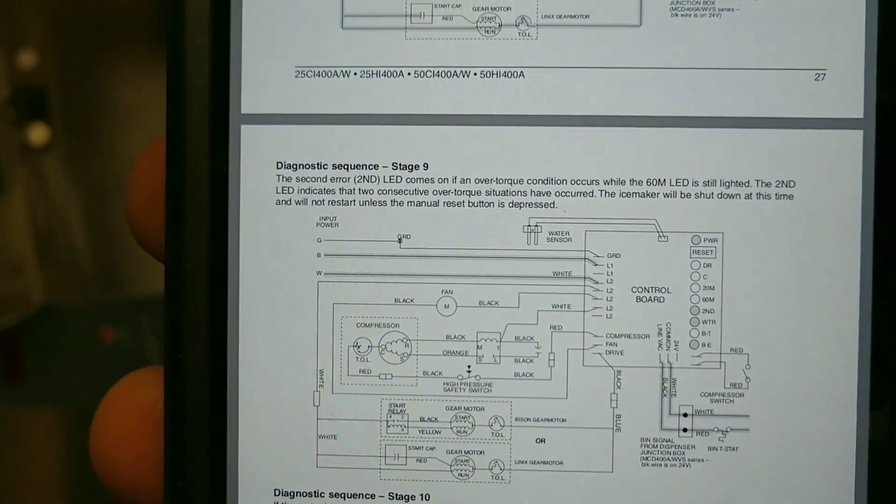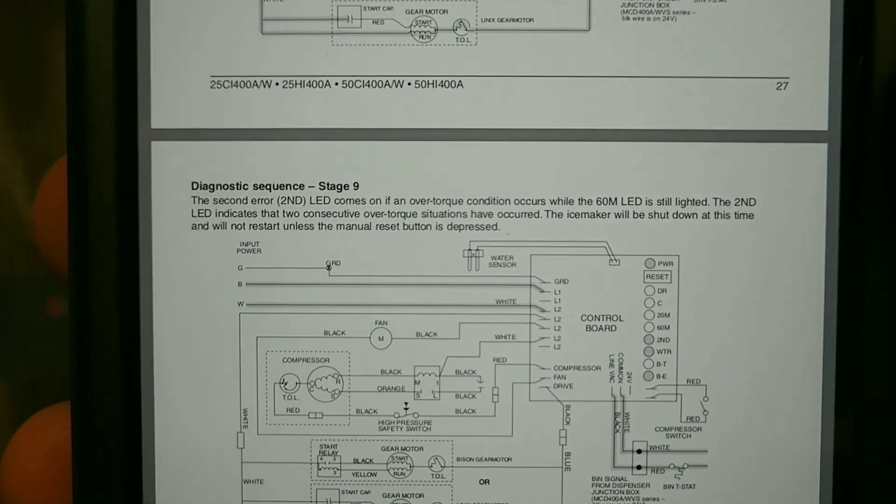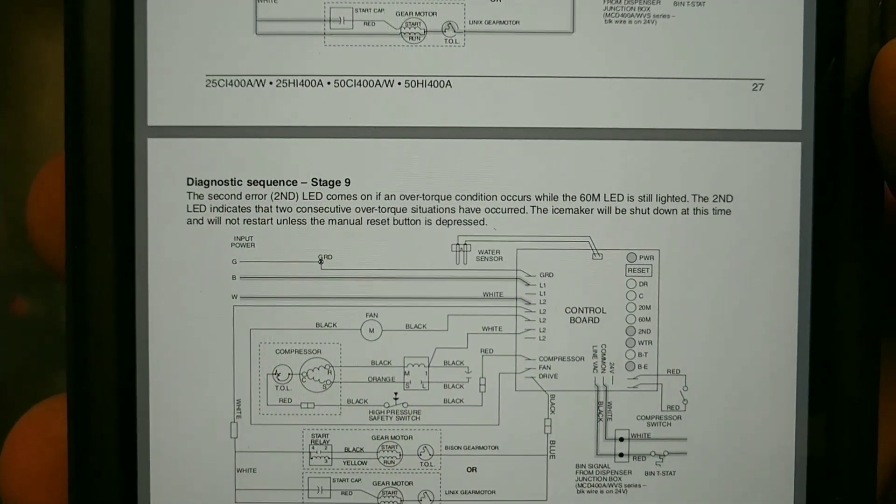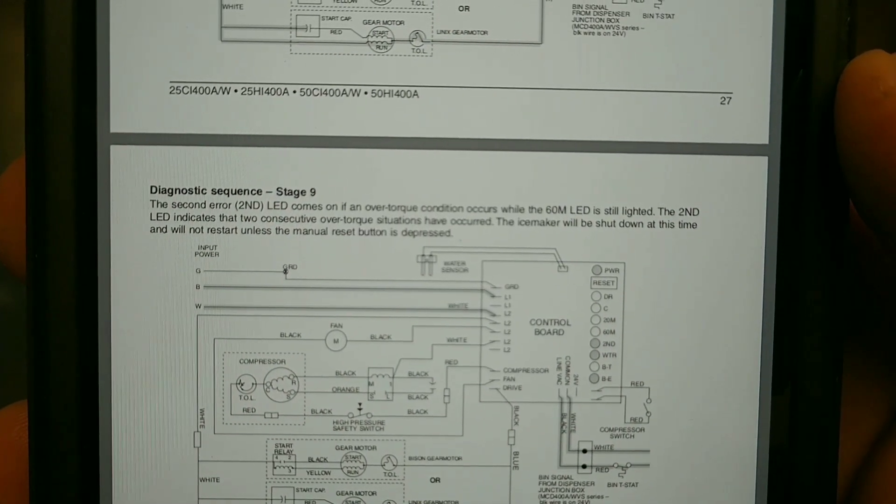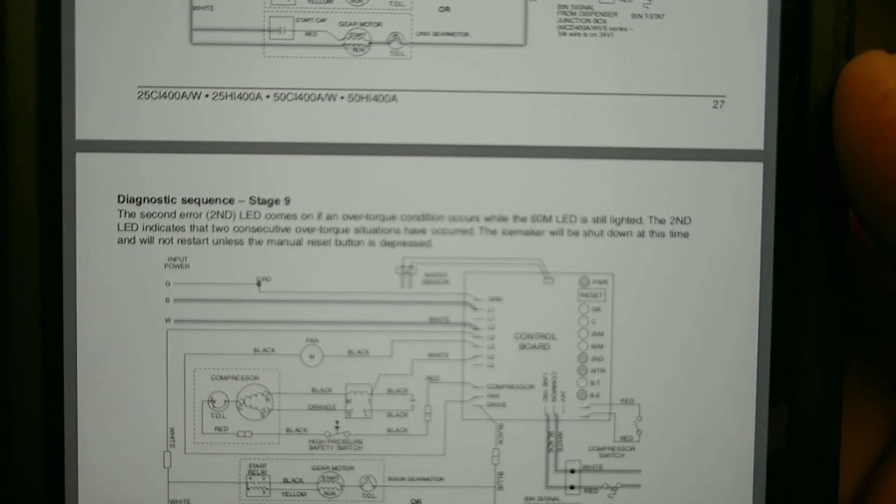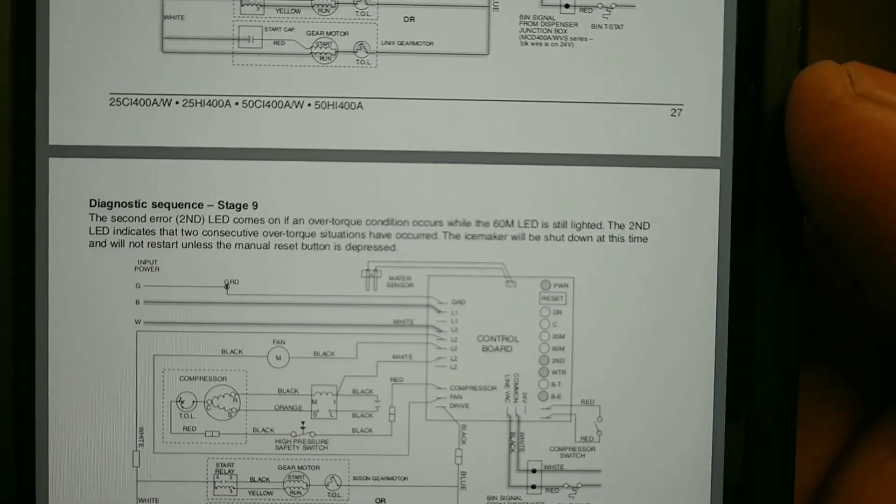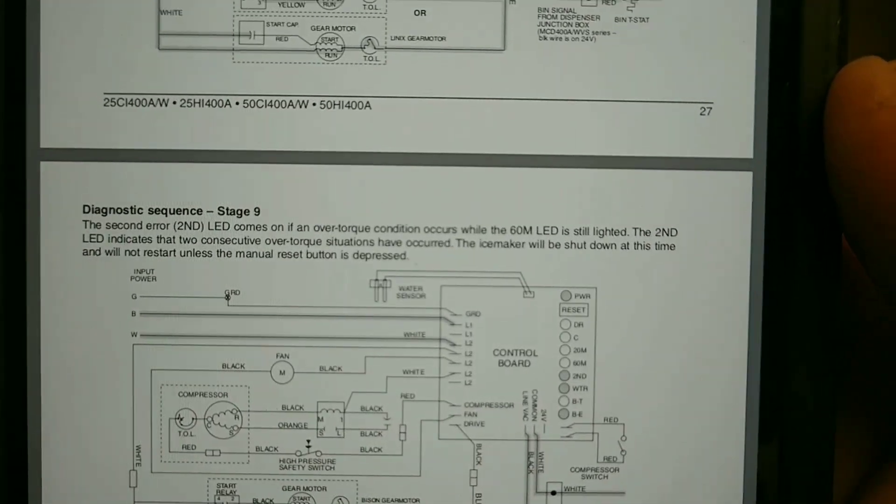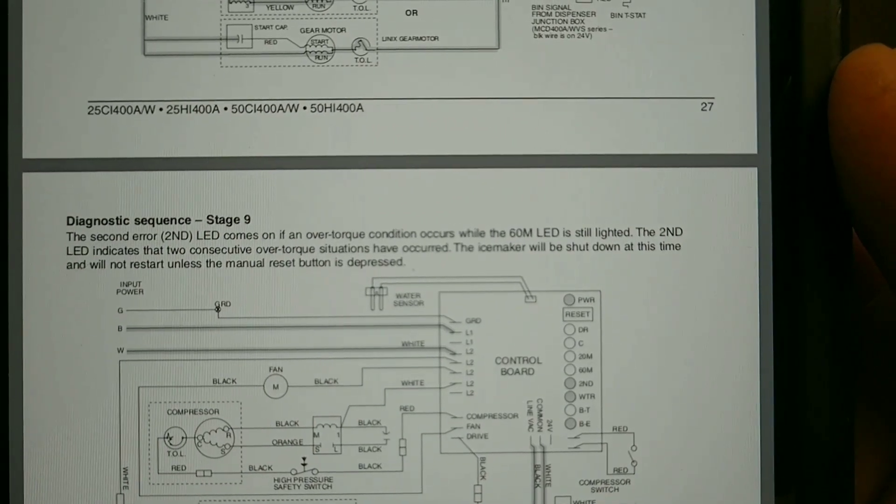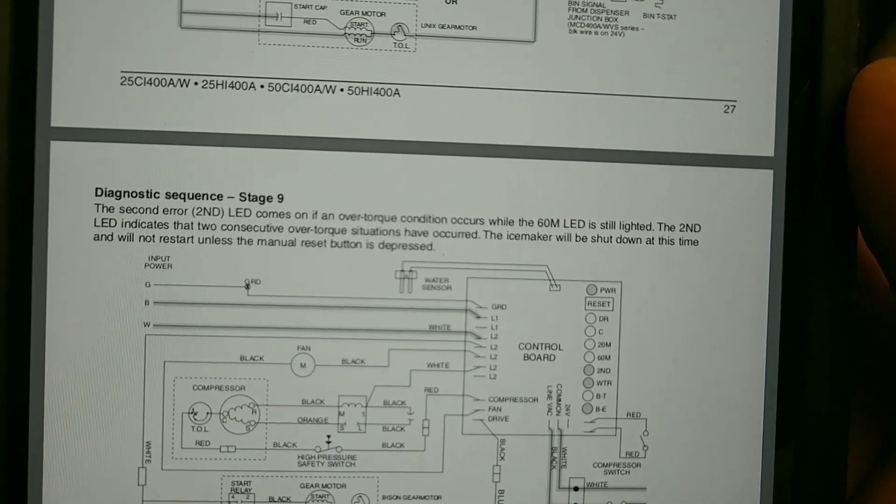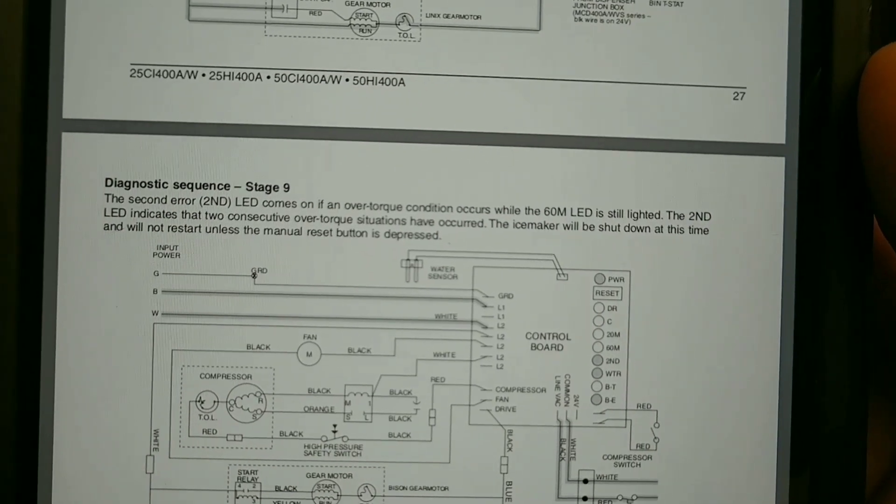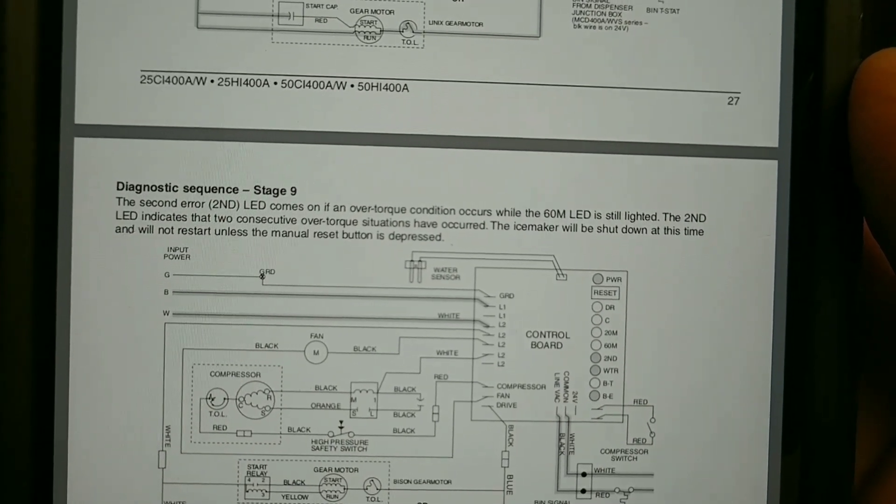But it didn't, because we also had our second LED. The second LED comes on if an over torque condition occurs while the 60m LED is still lit. The second LED indicates that two consecutive over torque situations have occurred. The ice maker will be shut down at this time and will not restart unless the manual reset button is depressed.